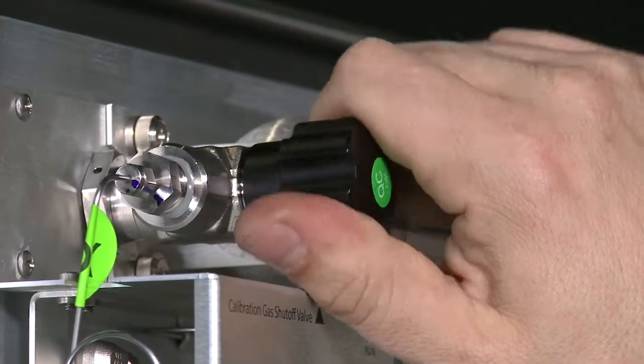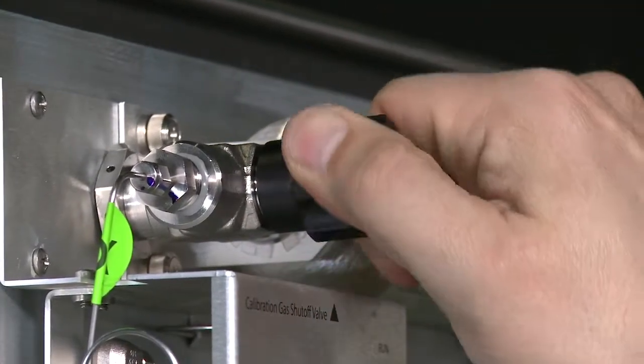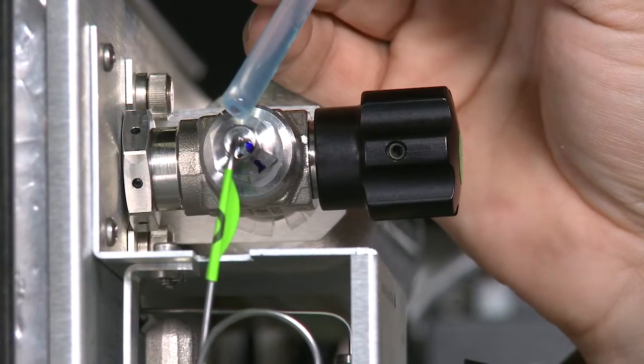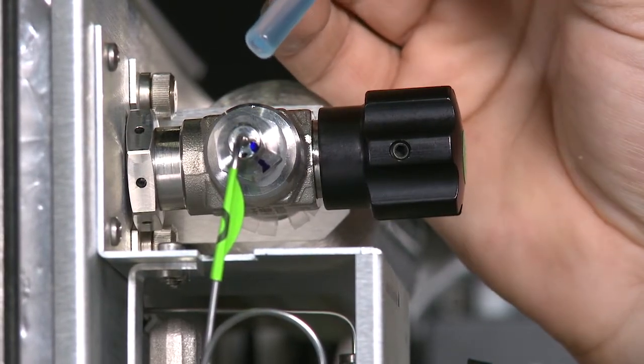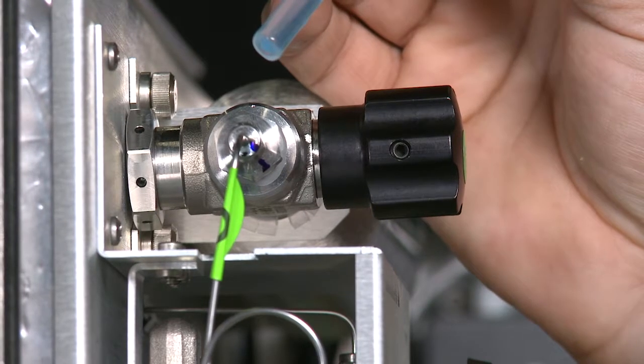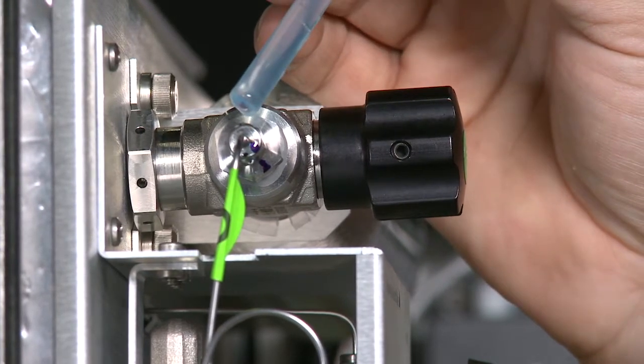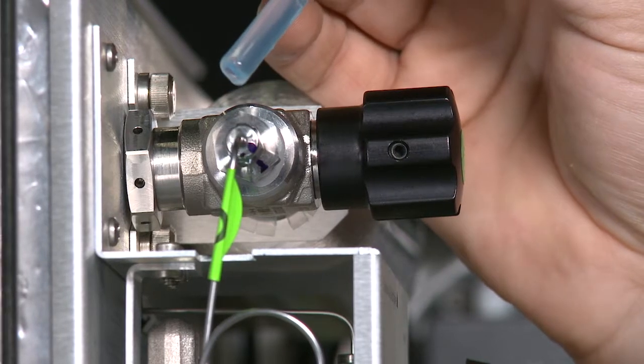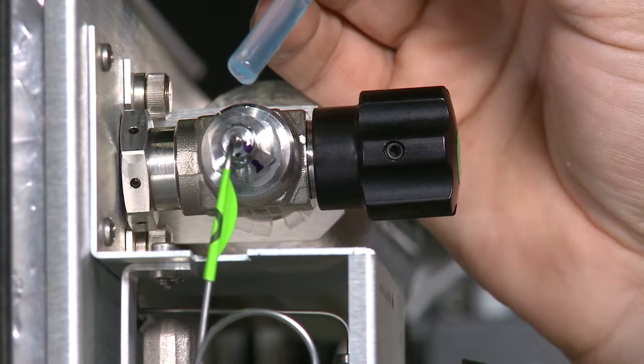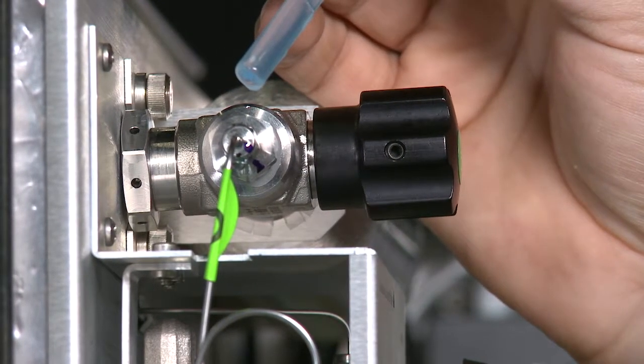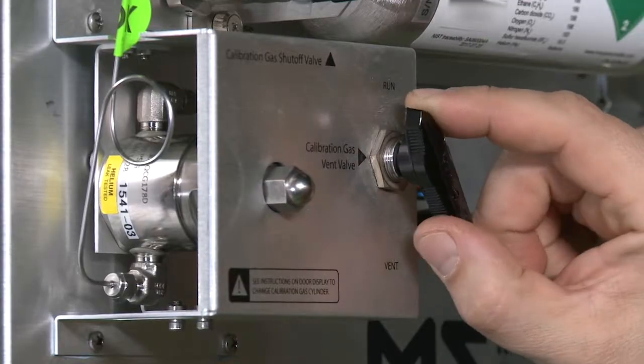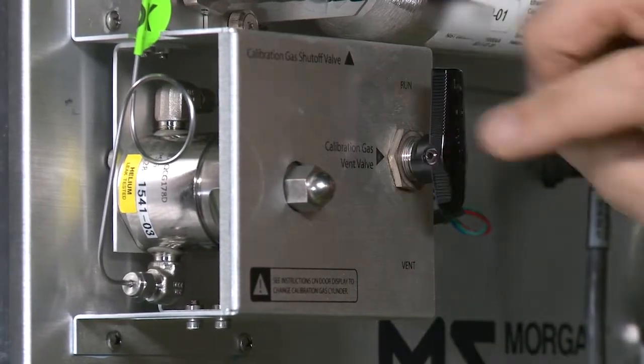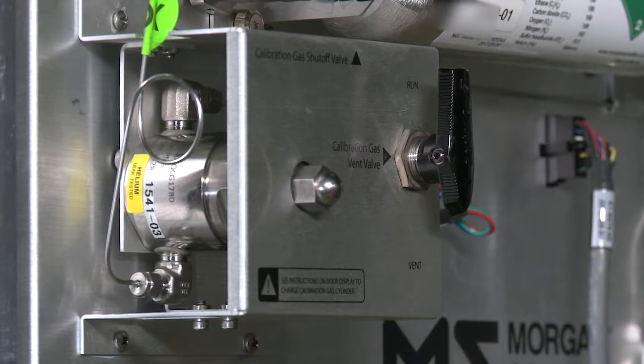Slightly open the cylinder shutoff valve, then close it as quickly as possible to pressurize the system. Use a helium detector or leak detection fluid to ensure that the connections are leak-tight. If a leak is detected, tighten the nut 1/16 to 1/8 of a turn. When everything is leak-tight, turn the valve to the vent position.